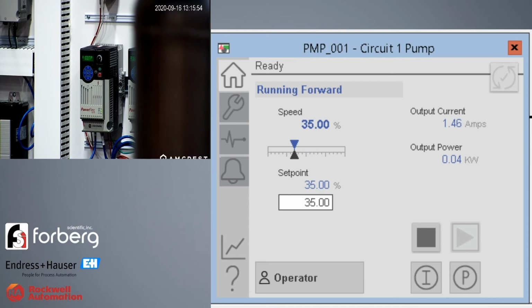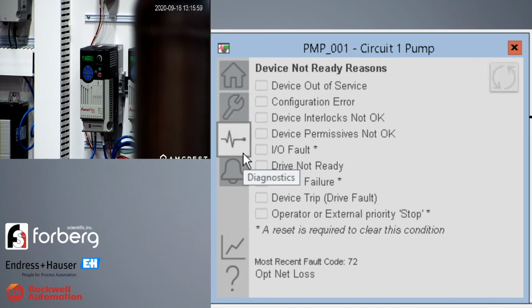As I open up the Diagnostics tab, Operations and Maintenance are presented with a list of reasons that the device is not ready to run, as well as the last fault code and the words that correspond to that fault. In this case, obviously, the device is running, so none of those particular faults are active. But you do notice down on the bottom, you get the fault code 72, which means there was a network loss, and that's presented in human readable words.